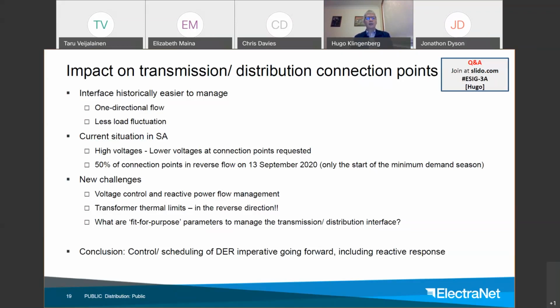That creates new challenges, which Elizabeth has covered off quite nicely, around what that means for voltage control and reactive power flow management at that interface. With the proliferation of non-scheduled generation, in our case we get quite a number of 4.9 megawatt connections in the distribution system, to the point that quite a number of our connection points are at risk of reaching transformer thermal limits in the reverse direction. From a system planning point of view, we're working with SA Power Network on what are the fit-for-purpose parameters to manage that transmission-distribution interface.